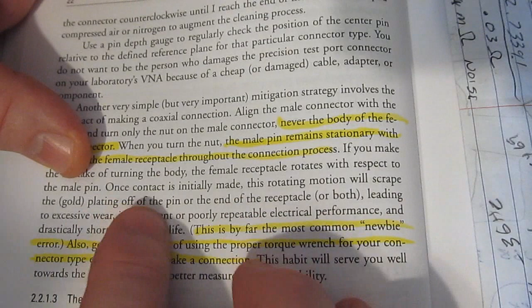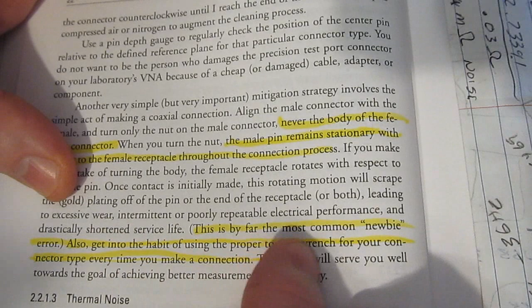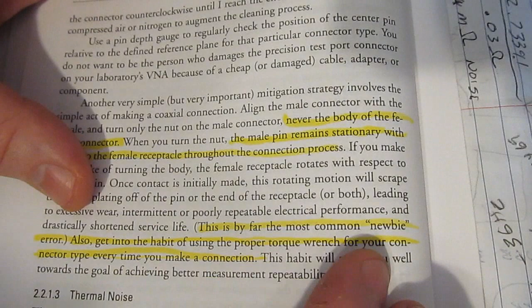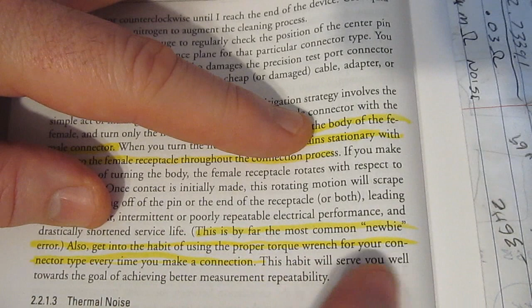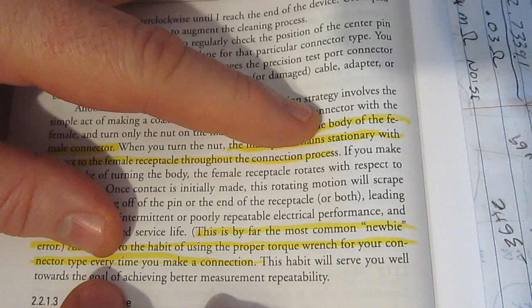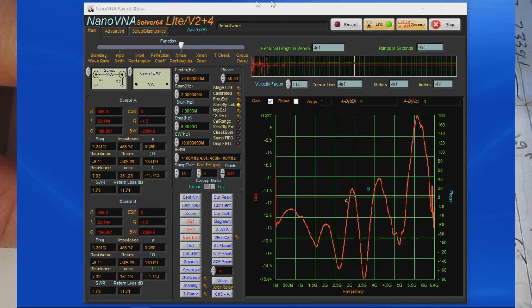Once contact is initially made, this rotating motion will scrape the gold plating off of the pin or the end of the receptacle, or both, leading to excessive wear, intermittent or poorly repeatable electrical performance, and drastically shorten the service life. This is by far the most common newbie error. Also, get into the habit of using the proper torque wrench for your connector type every time you make a connection. Of course, when I'm demonstrating these nanos, you don't see me using the torque wrench every time. Again, below about a gigahertz, I don't always use it, but as I start to work above that, you'll see me frequently pull it out. This habit will serve you well towards the goal of achieving better measurement repeatability.